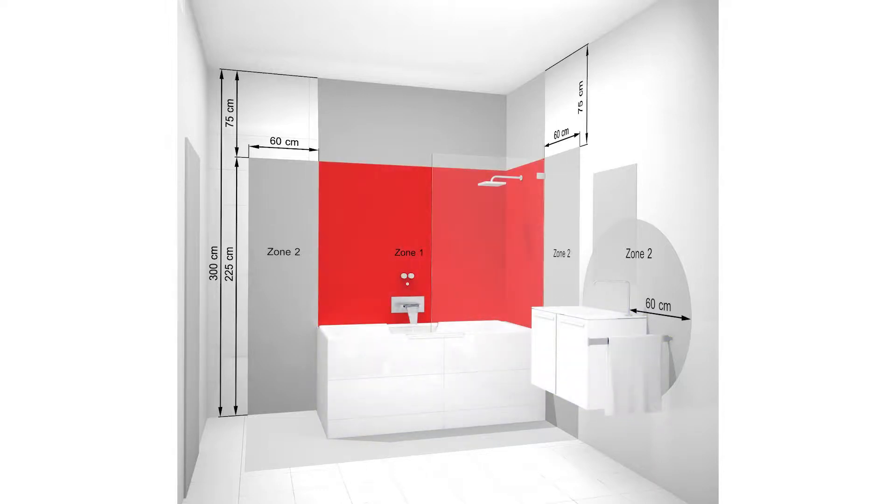The next zone is zone 1, and this refers to the area above a bath or shower walls to a height of 2.25 meters from the floor.